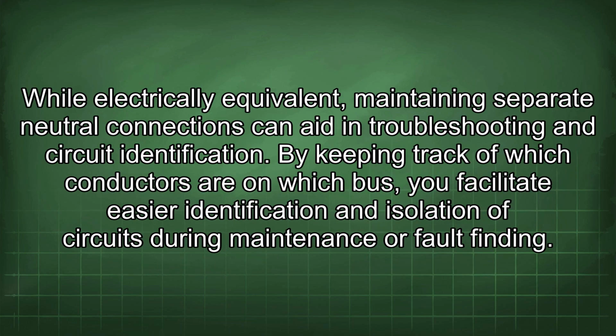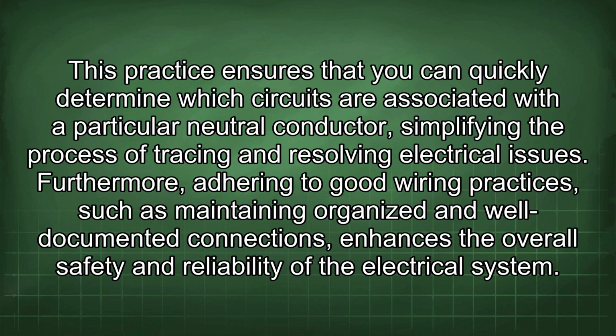While electrically equivalent, maintaining separate neutral connections can aid in troubleshooting and circuit identification. By keeping track of which conductors are on which bus, you facilitate easier identification and isolation of circuits during maintenance or fault finding. This practice ensures that you can quickly determine which circuits are associated with a particular neutral conductor, simplifying the process of tracing and resolving electrical issues.